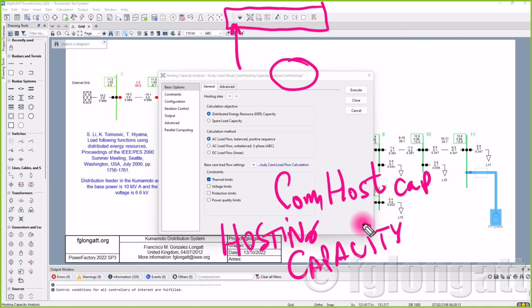I don't know if you realize, but I put in this network one PV system. And I went over there and I said 6.5 or 8 MVA. But nobody would say to me, come on, you don't do that like that. Nobody does that in serious and real situations. You must understand that the network has a capacity. The network has some MVA that the network can use. Beyond that, you are in trouble because you can trip the protections, you can overload the cables or the transmission lines, or you can go further up or down on the voltages.